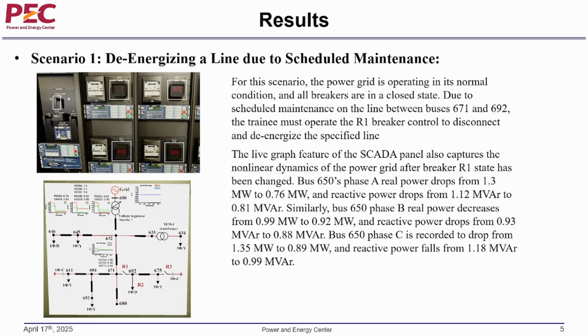For demonstration purposes, we are using the IEEE 13 feeder system due to the confidentiality of the VTES system. The first case is de-energizing a line due to scheduled maintenance. And this here is the metering system, and the one below here is the real-time SCADA system that we have developed in the VR environment. For this scenario, the power grid is operating in the nominal condition, and all breakers are in a closed state. Due to a scheduled maintenance on the line between bus 671 and bus 692, the trainee must operate the R1 breaker control to disconnect and de-energize the line.